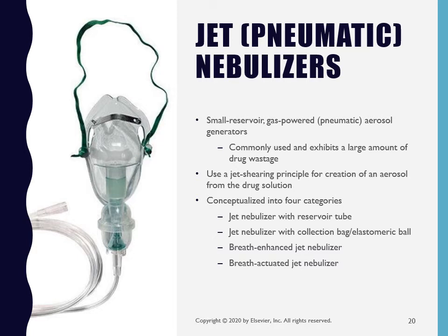The jet shearing principle is that an external source of compressed gas is directed through a very narrow opening inside the reservoir cup. The expanding gas creates a localized negative pressure and draws the drug solution up feeder tubes.